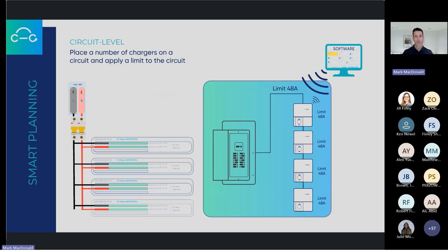or cloud-based or locally. So what that allows me to do, first car plugs in, pulls 48 amps. We're going to keep it simple again. By the time I get to the 4th car, they're each pulling 12 amps. So this is what we would call a single phase branch circuit load share. These 4 chargers are paralleled off the same branch circuit. This is the most cost-effective way to do it. It's not the most functional.